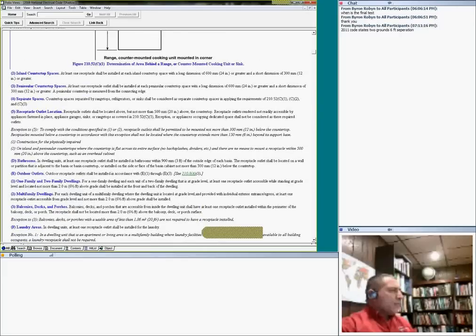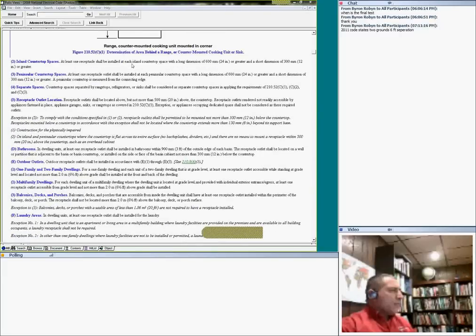I'd like to specify island, if you have an island, guys. An island, and these are all from the NEC code book, guys. Right directly here, grab this. 24 inches by 12. So if it's 24 or greater, and the short dimension is 12 or greater, then you need 1 receptacle. The same thing, guys: 24 by 12, 24 or more by 12 or more, then you need a receptacle.